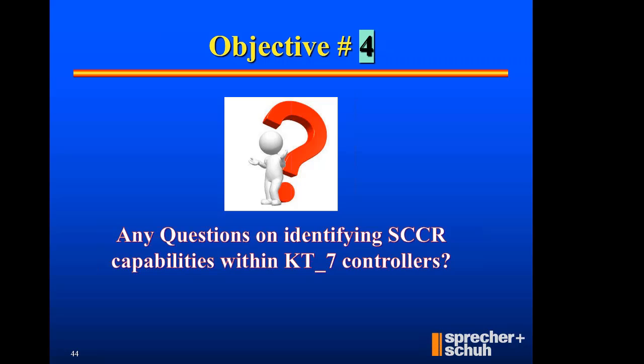All right, there's a couple of questions we've got. Is the entire unit 75 degrees C rated or 90 degrees C rated for the KTA7 or KT series? Okay, I heard you spit out some temperature values, but I've got to say that the contactor and the controller are merely going to comply with what UL says we need to comply with, which is up to 60 degrees C. 75 sure sounded hot. So I'll just reiterate the standard approval of the products themselves, which is going to be up to 60 degrees C.